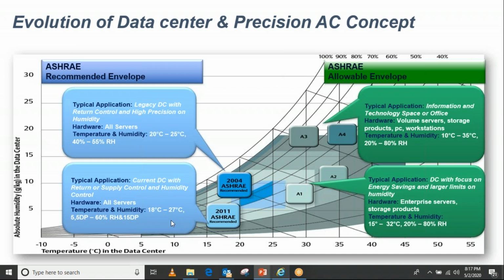So it's very important to understand that most of the users still are not familiar that in front of the electronics electrical room you can easily maintain 18 to 27 temperature in the front of the equipment, and then the discharge temperature is actually the return air which is coming back in the hot aisle. So we should not be bothered about what is happening on the hot side of the servers or the switch or the panel.